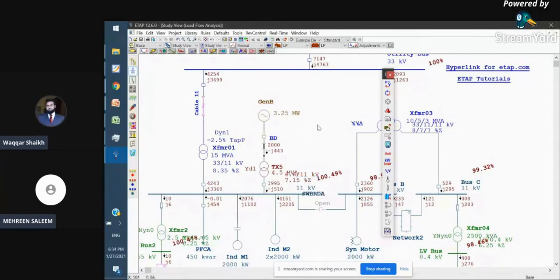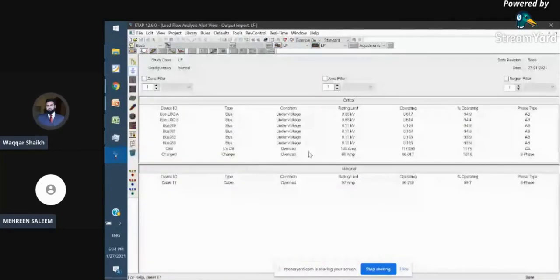If I click this option, it also shows me where those problems are occurring, the reasons, the set points, and the standard values. For example, it shows that at bus location A, we have an under voltage of 94.9%. The bus was originally rated 650 volts, but is operating at 617 volts. As per IEEE standard 399, we should not have lower than 95% voltage in the network after a successful load flow simulation, so lower than 95% is a critical alert, and we have to find ways to improve this voltage.